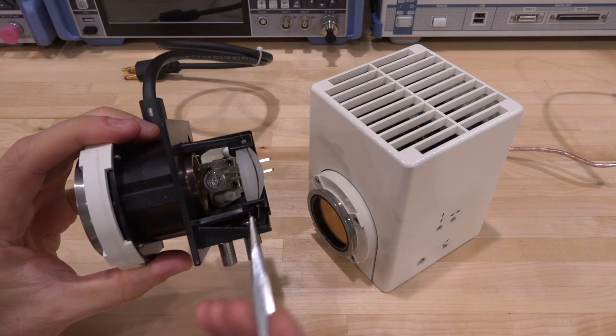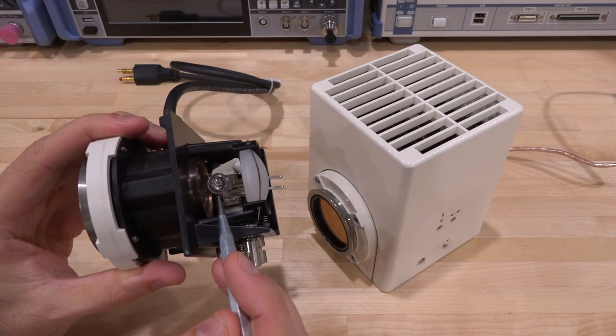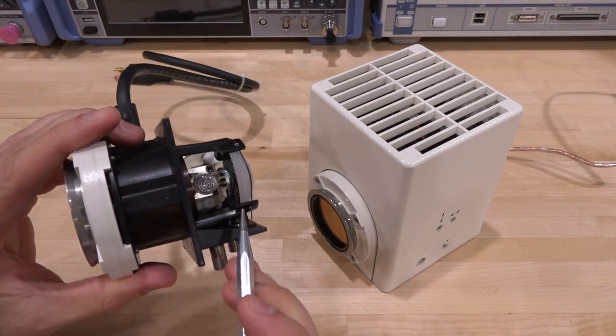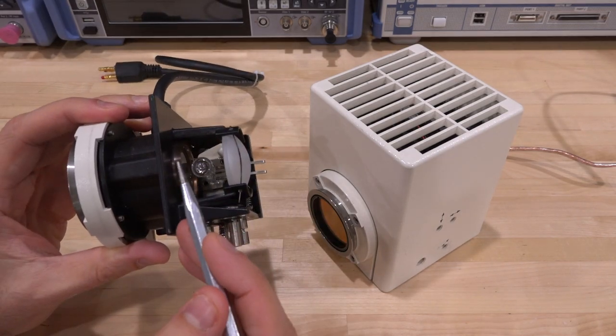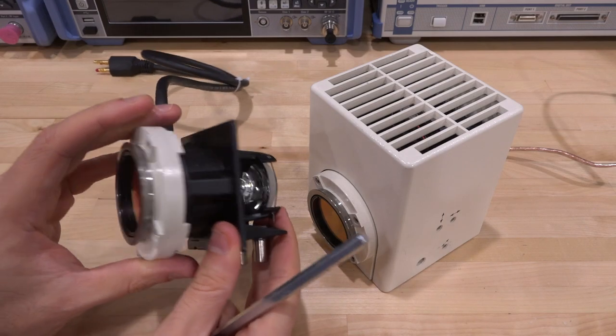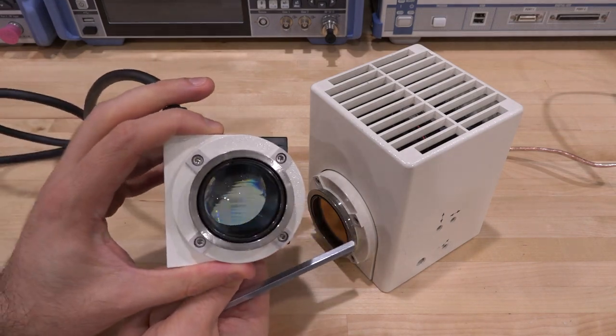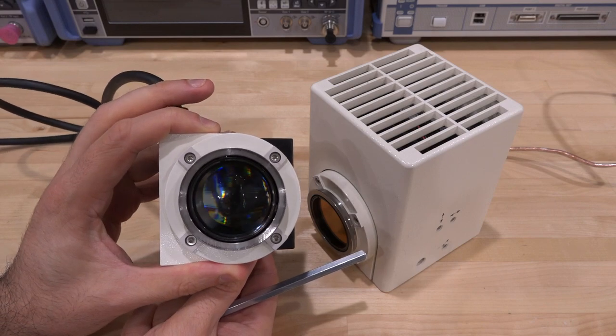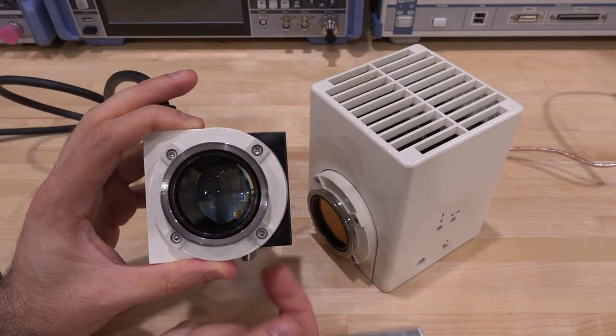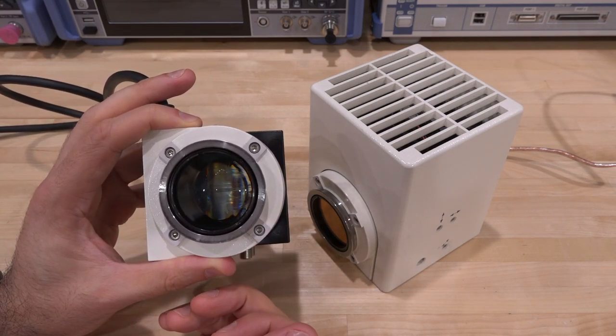Inside of it, you can see we find one halogen lamp, and the lamp has a mirror on one side. It's a reflective mirror, and it gets as much of the energy forward as possible through this aperture. If you look through the lens, you can actually kind of see the filaments in focus, and that's what you want. In order to get Kohler illumination from the light source, you want the filaments to be in focus.